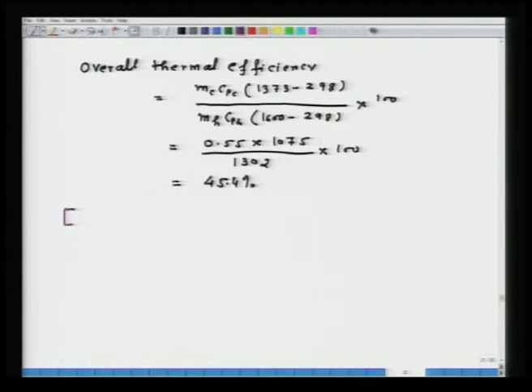of the heat exchanger. Now, another thing is that let us calculate efficiency limit. The physical significance of efficiency limit is very clear. That means, each heat exchanger has some upper limit to which it can exchange the heat of the hot flue gas to the cold air thermodynamically, because you cannot heat the cold air to a temperature above the temperature of the hot flue gas. Thermodynamically, it is impossible. That is what the physical significance of efficiency limit is, and we have seen in the formula that the efficiency limit simply becomes equal to MC CPC upon MH CPH into 100. The temperatures from both the sides, numerator and denominator, cancel. So, the efficiency limit in this particular case is equal to 55%.